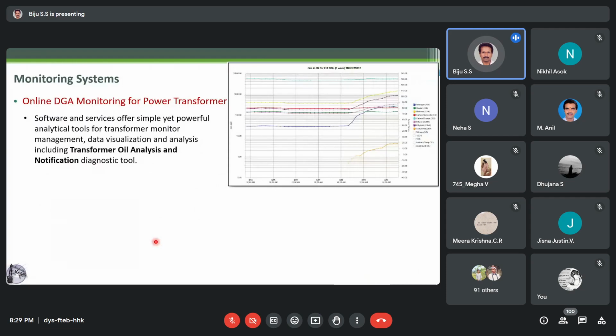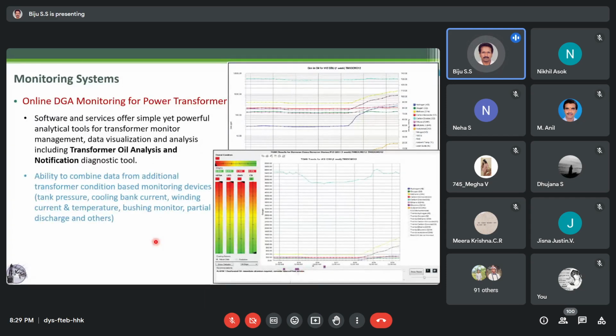Now, online DGA is another technology which is being used now. Dissolved gas analysis for transformers. The analytical software will, once you capture the data, do an analysis and give a notification also at what sort of fault has taken place, what's the gas content in the oil, and what are the different gases that are there, and those things will be monitored. And it can also combine with additional transformer condition-based monitoring devices like tank pressure, cooling bank current, winding current and temperature, bushing monitor, partial discharge. So these things can all be combined together to give a condition-based assessment of the transformer. So nowadays, systems are not standalone. They can take inputs from other data also, from other systems also, and do the analytics.